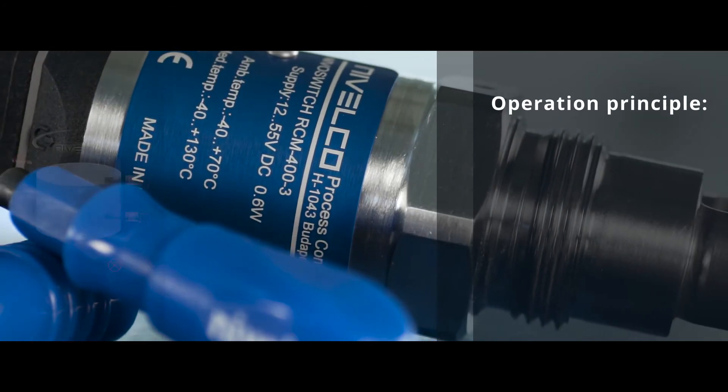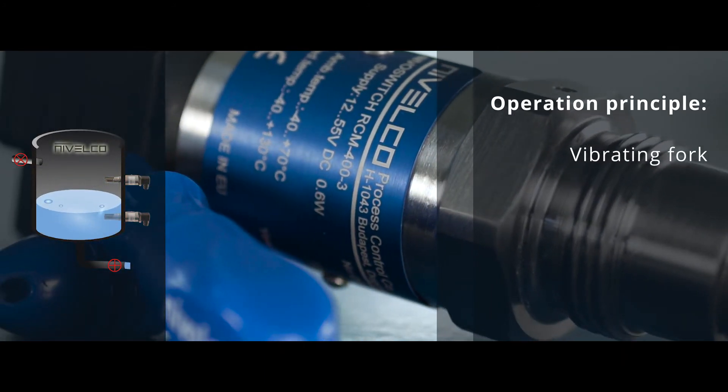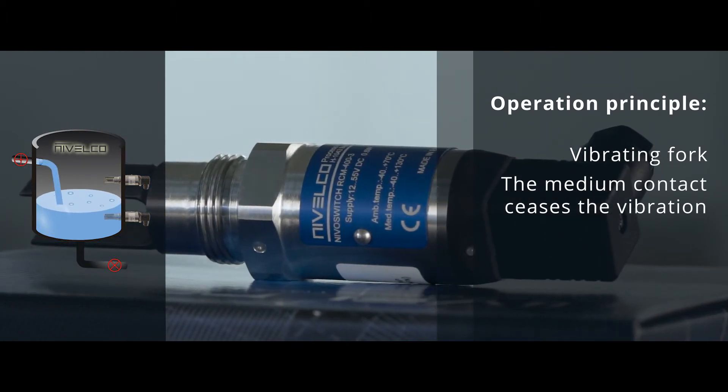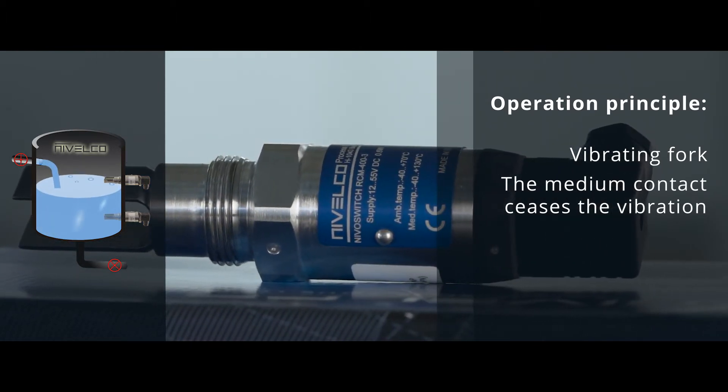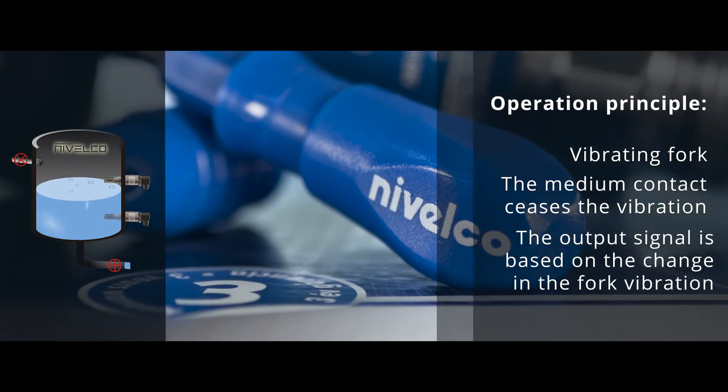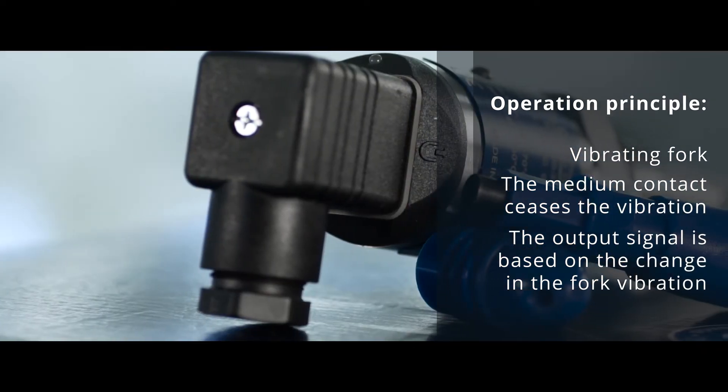The operation principle is based on that the electronic circuit excites a vibration in the fork probe. When the medium reaches and covers the fork, its vibration changes or stops. The fork will start vibrating again as the medium sets it free. The electronics sense the change of vibration and give output signal after a selected delay.